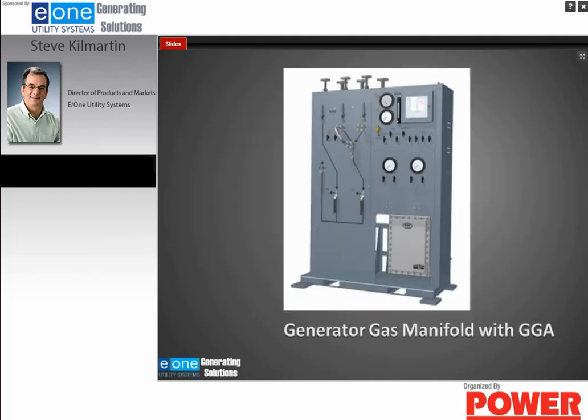This is a typical hydrogen control cabinet. In the upper right-hand corner, that's the gas analyzer. Again, you have fan differential pressure gauge, case pressure gauge, a flow meter to monitor the flow into the analyzer control and display panel. Also on this, below that panel, you see the CO2 supply pressure, hydrogen supply pressure, and then to the left-hand side is the manifold that is used to put the gas in and out of the generator.